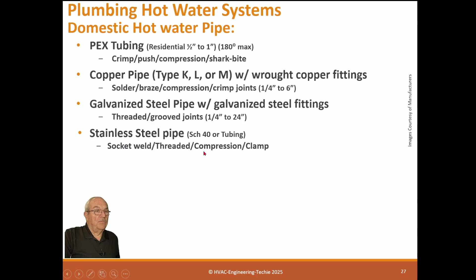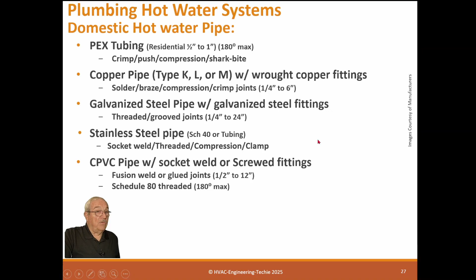Socket weld, threaded, compression, clamps. CPVC pipe with socket weld fittings, fusion weld or glue joints, 1/2 to 12 inch, and schedule 80 threaded, 180 degrees max again. So remember, what's not on this list is PVC, because it won't take any temperature at all. So we normally don't allow PVC for domestic cold water or hot water.